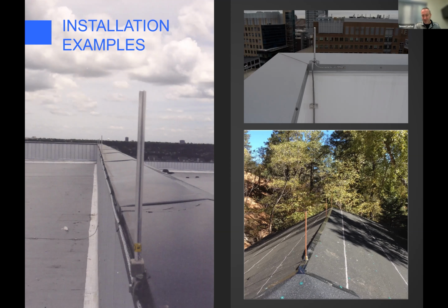And then of course we've got the ridge, because there's no metal there, it's just going to be a shingle roof. You can use the copper, which is more conductive. So we tend to use that if we can, but if we can't because of corrosion issues, we'll use the aluminum. The one thing to note about aluminum versus copper, engineers love to say you have to use copper all the time in a lightning protection system, but I go out and inspect older systems that used all copper, and I can see that underneath the lightning protection material, the parapet's just starting to rust through. I see that all the time, and I make recommendations for new lightning protection systems that you always have to take the materials into account.